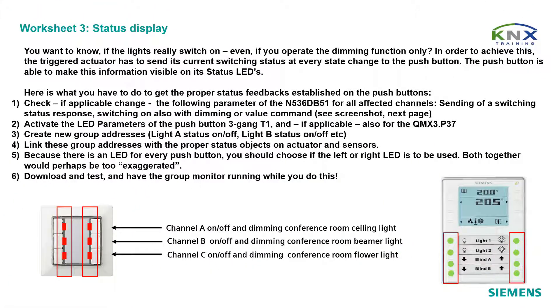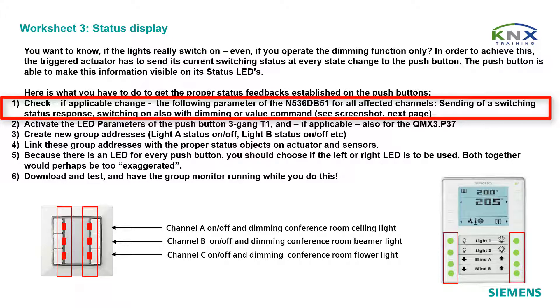Status display. You want to know if the lights really switch on, even if you operate the dimming function only. In order to achieve this, the triggered actuator has to send its current switching status at every state change to the push button. The push button is then able to make this information visible on its status LEDs. Here is what you have to do: check and if applicable change the following parameter of the N536DB51 for all affected channels — sending of a switching status response, and switching on also with dimming or value command.